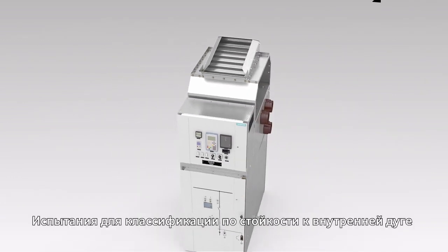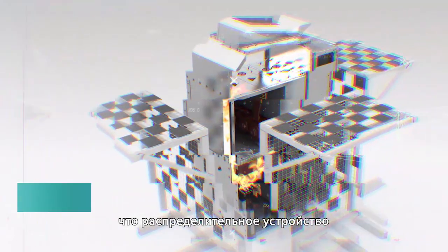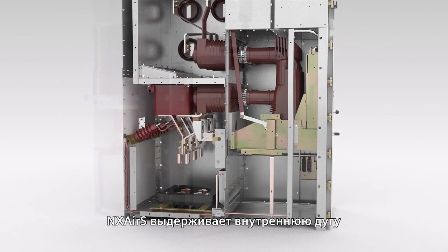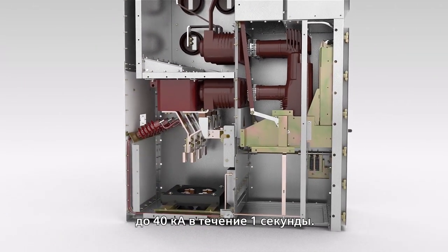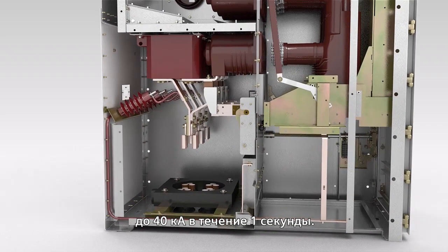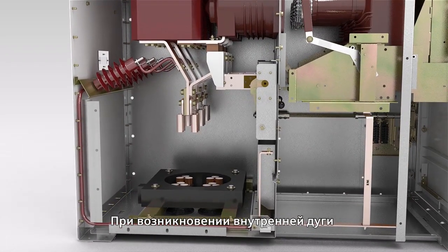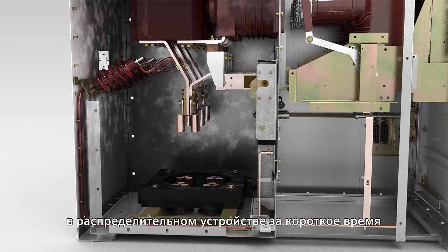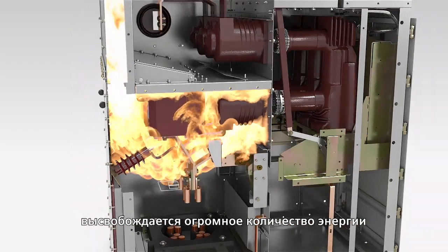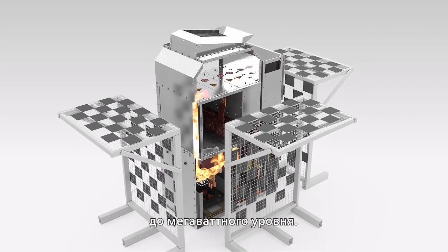Internal arc classification tests are one of the most rigorous type tests. It verifies the effectiveness of switchgear design in protecting personnel in case of an internal arc. NXAirS withstands internal arc up to 40 kA for 1 second. When an internal arc fault occurs, a large amount of energy up to megawatt level will be released within a short period of time inside of the switchgear.